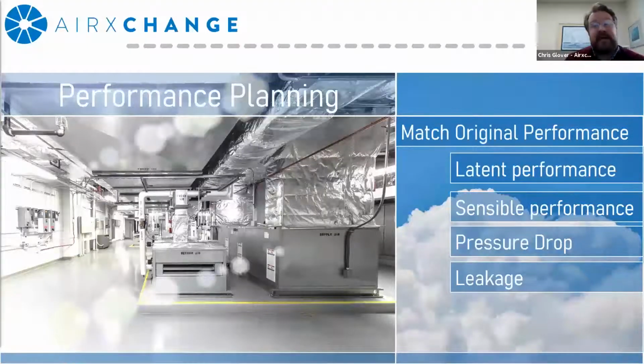Okay, so let's say you identified a potential for repair or replacement. What's your next step? Since this device is part of an existing system, the most important aspect of replacement is to either match or exceed the original design. That way the system can operate as it was initially intended. This includes sensible performance, latent performance, pressure drop, and leakage, all of which are AHRI certified, I should say. So you may be asking yourself at that point, am I intuitively supposed to know all that? And the answer is no, you're not. That's why Glenn and I are here, to provide that level of support.